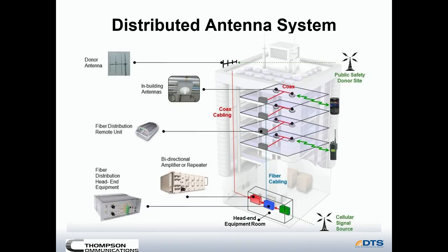Here's a block diagram of a DAS system. It starts out with the donor antenna, which is called a YAGI. This is a very directional antenna and points directly at the donor site. This is a public safety site in this particular drawing. This DAS system also has cellular, and that donor site is indicated down here. Once the signal comes in through the donor antenna, it travels through coax down to the BDA or the repeater.